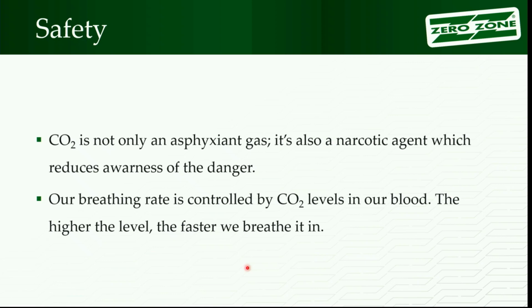So if you start having that, you don't want to wait till the last minute because, depending on your mind, you may have a hard time understanding where the door is, how to get down, get up a staircase, do whatever. The advantage, though, with CO2, is that as we get CO2 levels in our bloodstream, our heartbeat and our breathing start speeding up. So we have kind of a self-monitor. Again, you're working with CO2, you've got to respect it. If you start noticing, boy, you're breathing pretty fast, and you didn't really do any extra work, you're only turning a wrench, you're just standing there watching the controls, and you're noticing your breath or your heartbeat picking up, you really want to start looking for the door, go out and get some fresh air, right? You don't want to look for the leak until you get some fresh air.